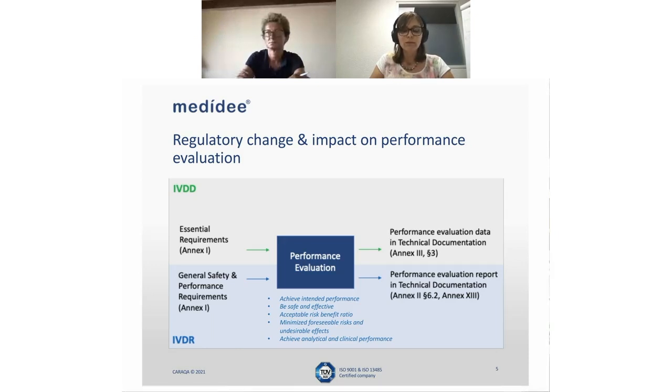And this is basically to demonstrate that the device achieves its intended performance, that it is safe and effective, that there is an acceptable risk-benefit ratio, that there are minimized foreseeable risks and undesirable effects for these devices, and that the analytical and clinical performance of the device is achieved.